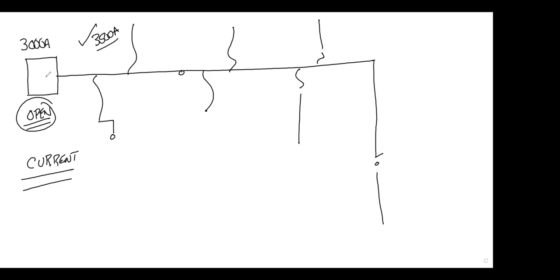Okay. Once I close the breaker, is this load still here? Closed now. Once it's closed, yeah, it's going to trip. From what? Overcurrent or overload? Overload. Okay, actually both. Because the overload is going to cause an overcurrent. There you go. That's why I said about five minutes ago, they're the same. With a closed breaker. Okay, got it.